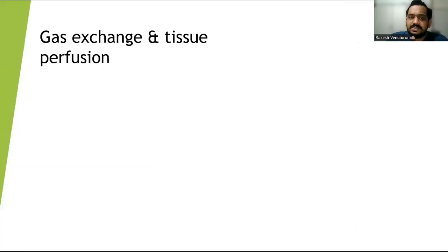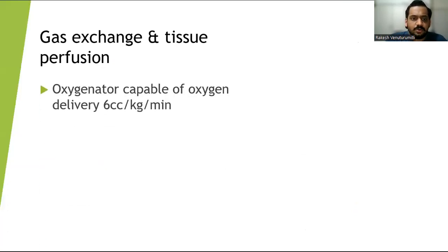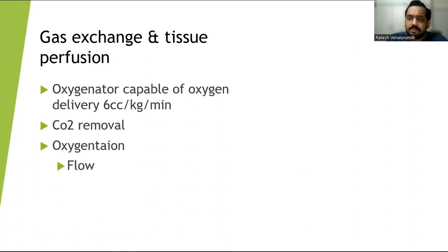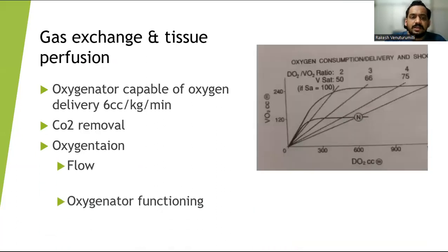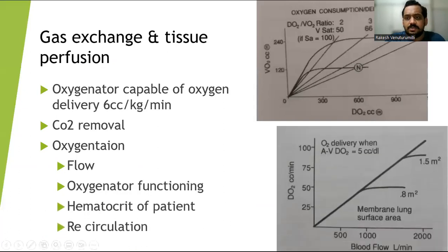Coming to how you optimize your gas exchange and tissue perfusion, as we all know, you should select an oxygenator that is capable of delivering oxygen, a minimum of 6 ml per kg per minute, and it should be equally capable of removing carbon dioxide. Let us see how we are going to affect this. If you see this graph here, the oxygenation is mainly dependent upon your flow, the oxygenator functioning, the hematocrit of the patient, and the recirculation of the patient.